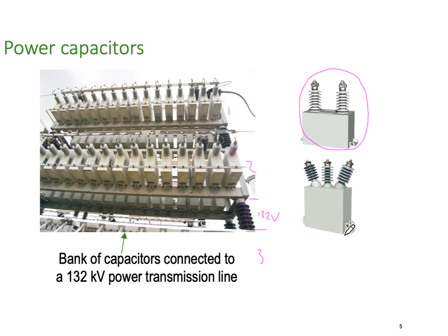And over here we have what's called a tapped capacitor. So we can have a common and then a couple of tappings that we can switch in, because quite often these large capacitor banks in high voltage substations are used to do voltage and network correction on the network, and they switch in the banks as required.